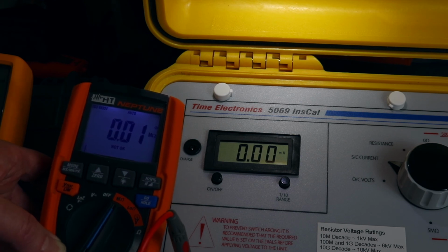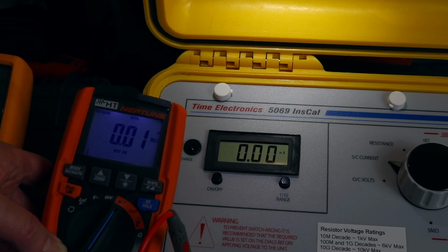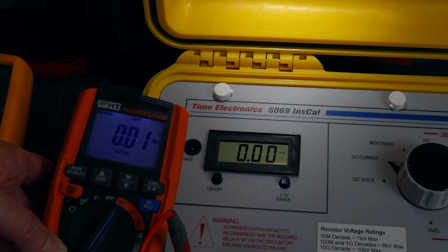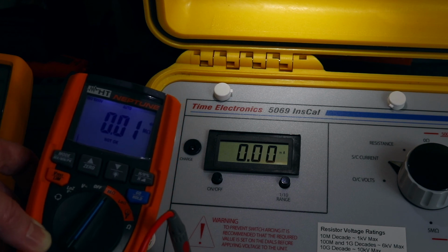At higher resistance values it's fine, you don't hear that resonance. Now if this was a switch mode power supply you'd perhaps be concerned about that because you don't want your HT transformer resonating in that manner, that'll wear it out. With this being an insulation tester, the amount of times it will pick up a short circuit anyway, it's not really that big an issue, but it does point to resonance within the instrument that you don't usually hear.